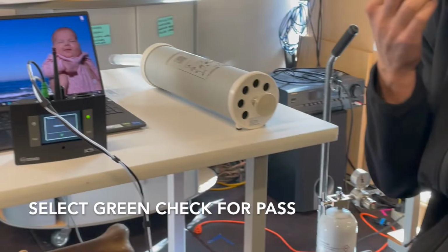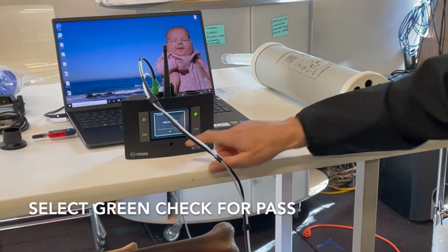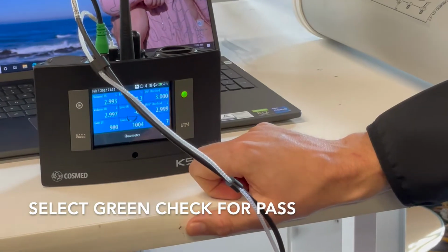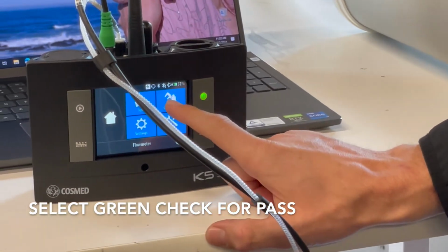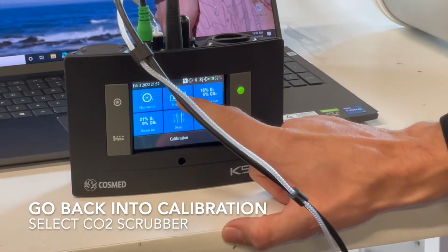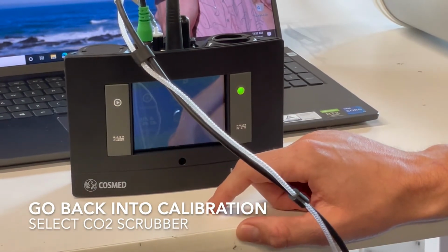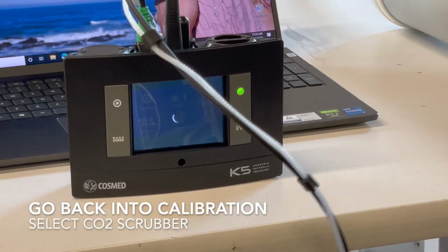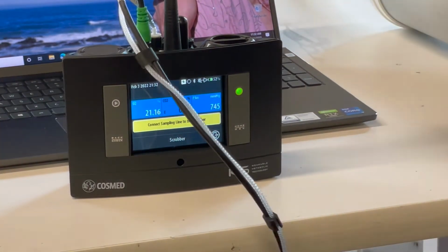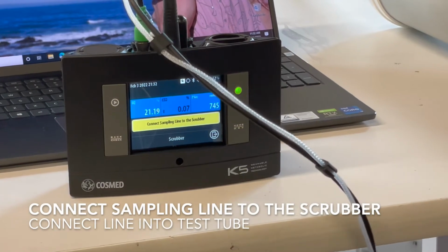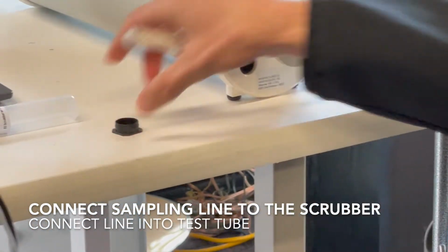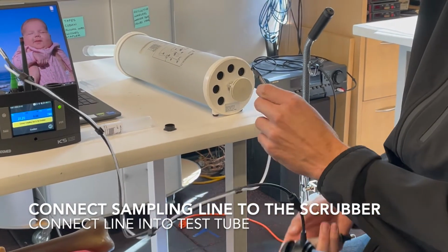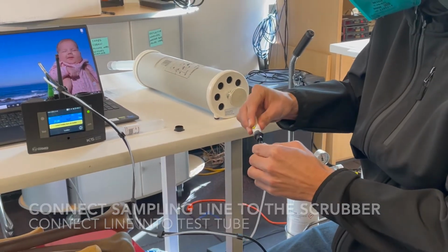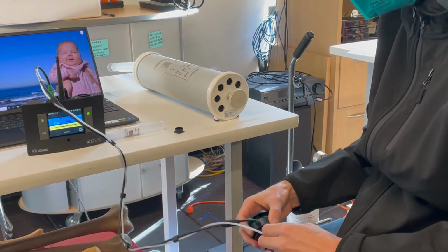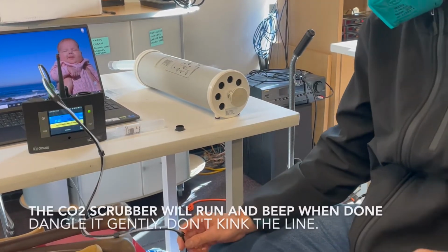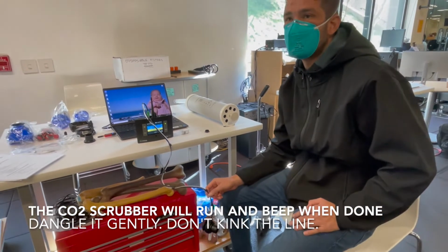It just said calibration pass. It's just a pass-fail criteria. So we'll hit the green check. We're good to go. We're going back into calibration, and now we're going to do the CO2 scrubber. It's just going to say connect the sampling line to the scrubber. So you take that, plug it right in there, and let it just hang out. It'll run, and it'll beep at you when it's done, same thing, pass-fail criteria.